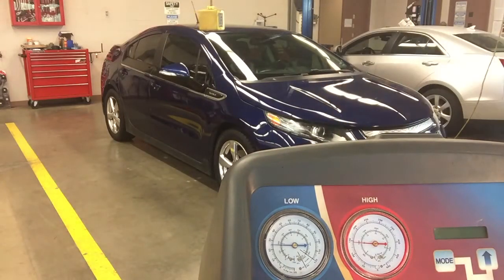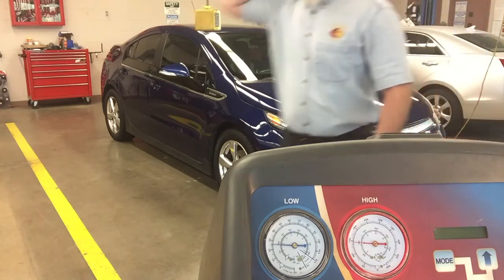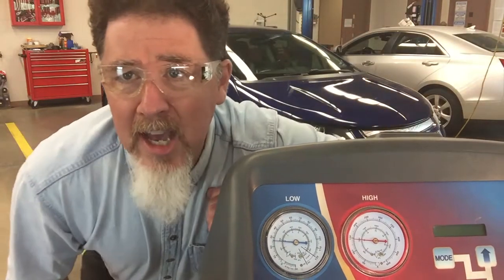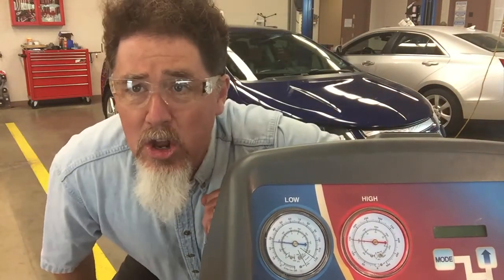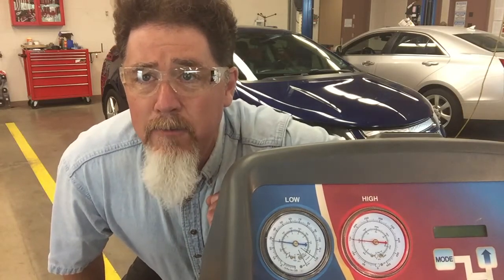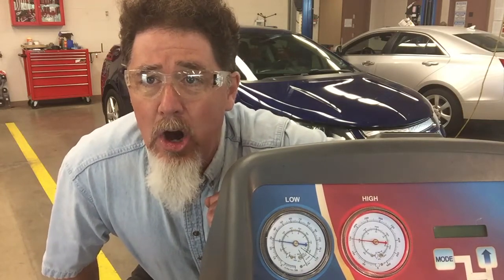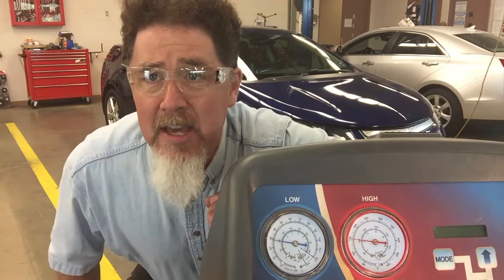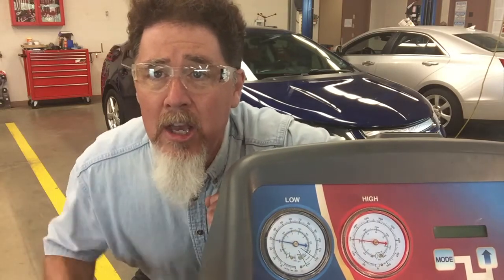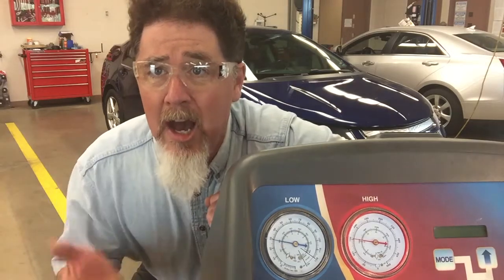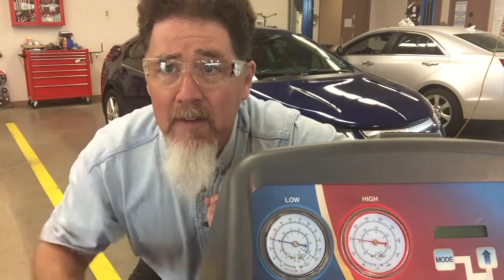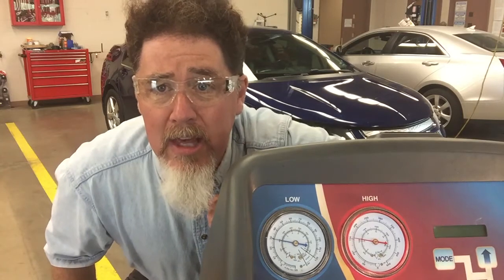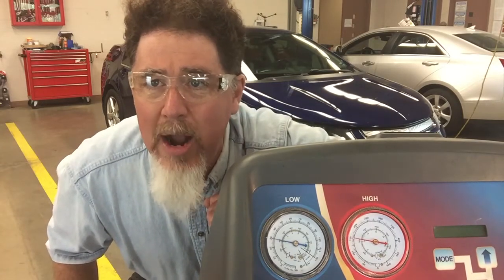So here we go. Okay, so all I did was turn on the rear AC unit to full high, and with the front and rear AC unit now on, that's going to give the AC system more of a heat load. That rear evaporator is absorbing more heat. It's actually raising the pressure of the suction line, and so we should be able to see that suction pressure looks like it went up to around 30.